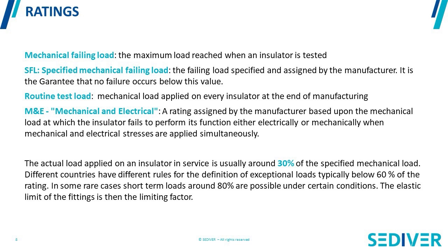There is another definition which exists mostly for porcelain insulators. It's what we call the M&E, which is described in American standards. The M&E is a rating which combines an electric stress and a mechanical stress.